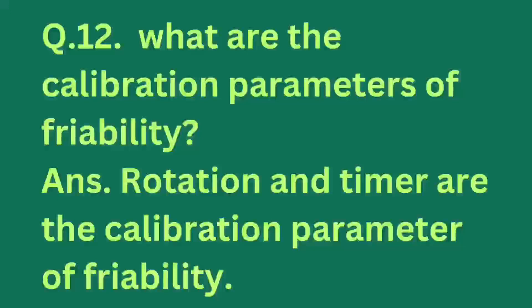Next question: What are the calibration parameters of the friability tester? Answer: Rotation and timer are the calibration parameters of the friability tester.